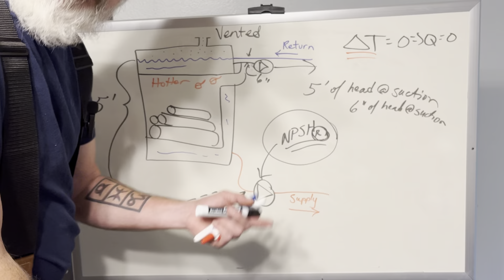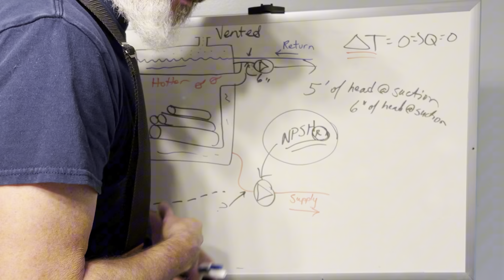Counterflow, the water coming back this way is going to be colder, and it's going to be exposed to the hottest point, so that temperature gradient is going to be the highest for the longest amount of time inside that boiler. Better heat transfer. Now it's not going to be a night and day difference, like oh my gosh, I cut my wood supply in half, but that's one reason. It's a higher delta T of the water and the firebox temperature.